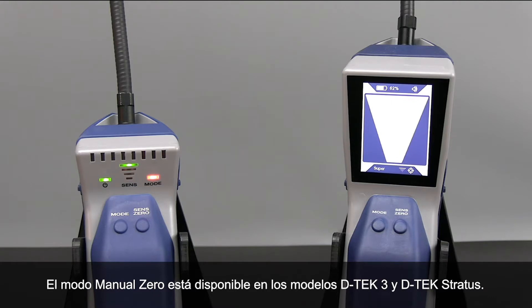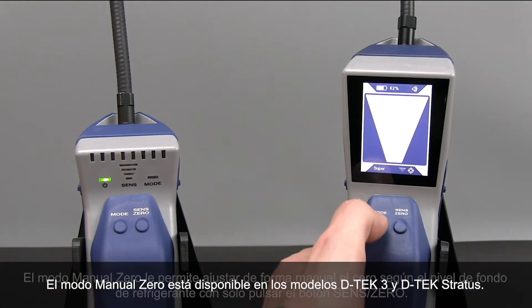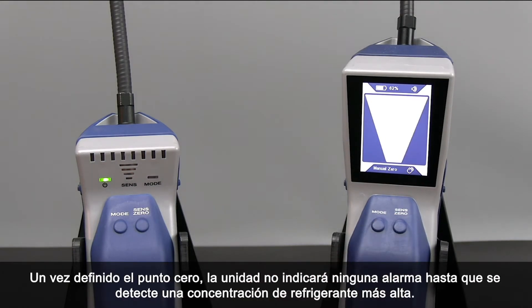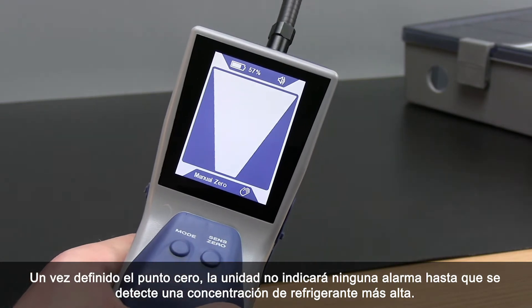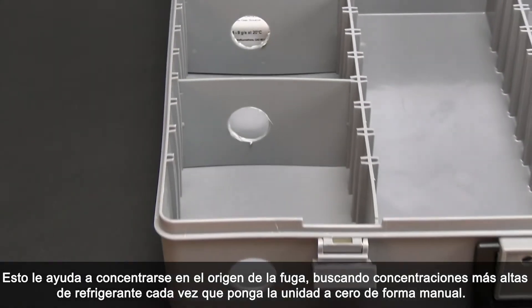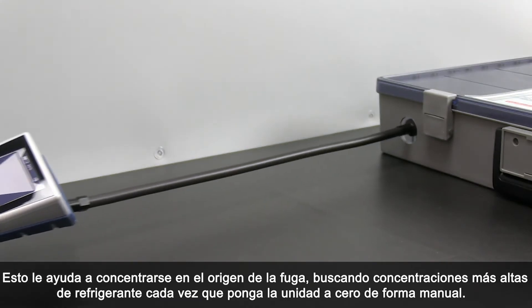Manual Zero Mode can be found in the D-TEK 3 and D-TEK Stratus. Manual Zero Mode allows you to manually zero to the background refrigerant by pressing the Sense Zero button. Once a zero point is set, the unit will not alarm unless a higher concentration of refrigerant is detected. This helps you hone in on the source of the leak, searching for higher concentrations of refrigerant each time you manually zero the unit.